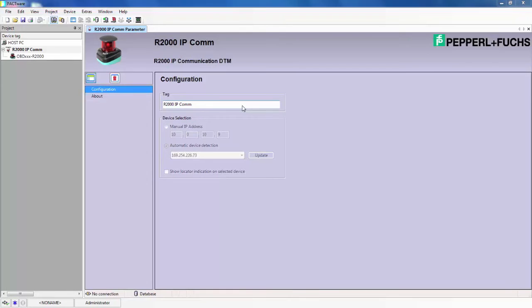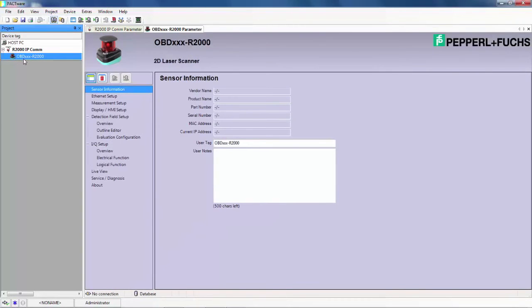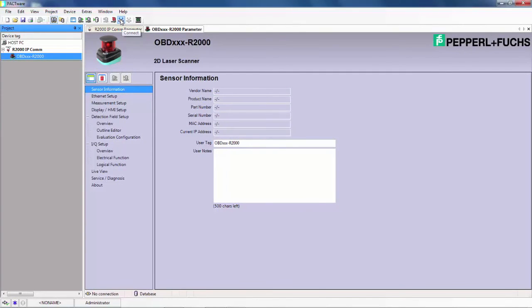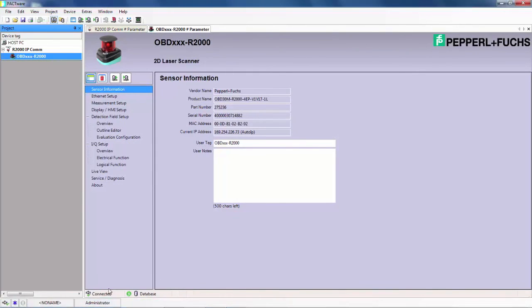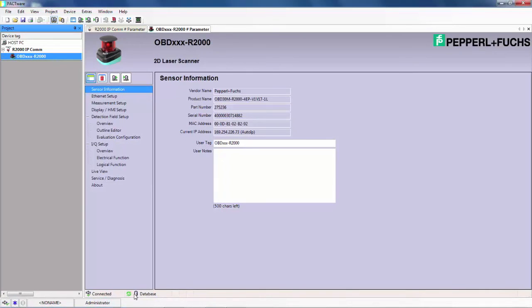Once you are connected to the IP communicator, the next step is to find the OBD R2000 in the project window and double click it. The parameter window opens up in this main window. Now the last thing to do really is press the connect button. If you connect properly, you will see a green swirling icon that indicates the R2000 is communicating properly.